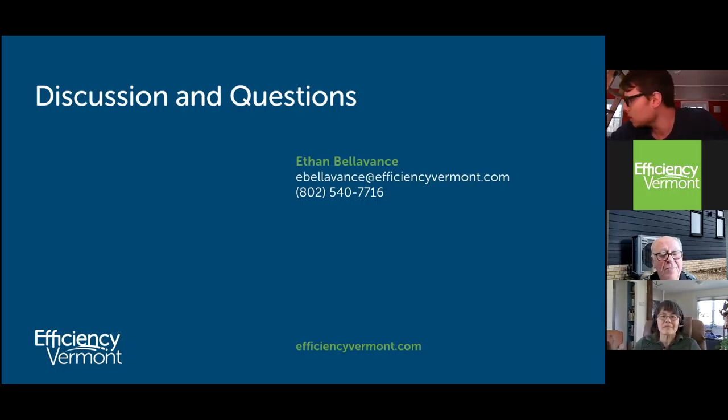Awesome. Gary, one question that I have, and I'm curious on your opinion on this, is triple evacuation procedures for new installations, and really curious on the view of the value of that for new systems. It sounds like there's probably value on the service side, but do you see value on new installations or not? I see it as a time waster on a new installation. I would not do a triple evacuation unless I had a feeling that I had a service problem. I had maybe water in the system that I was aware of, or a real bad burnout. I would probably try a triple evacuation to help. Triple evacuation is, I know, recommended in certain instances.